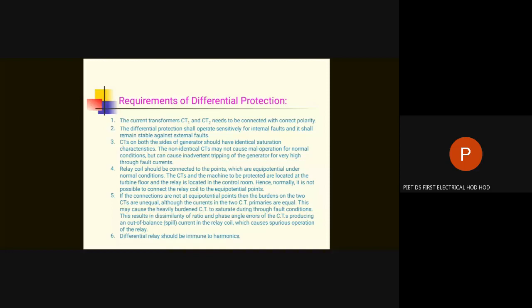First requirement is this. The second requirement is, the differential protection shall operate sensitively for internal faults, and it shall remain stable against external faults. This is a very important requirement, that the protective scheme is only for internal faults. External faults are certainly faults. They are also dangerous, but differential protection should not operate for external faults. The differential protection means that there is something wrong within the generator, and you have to take care of anything that happens within the generator.